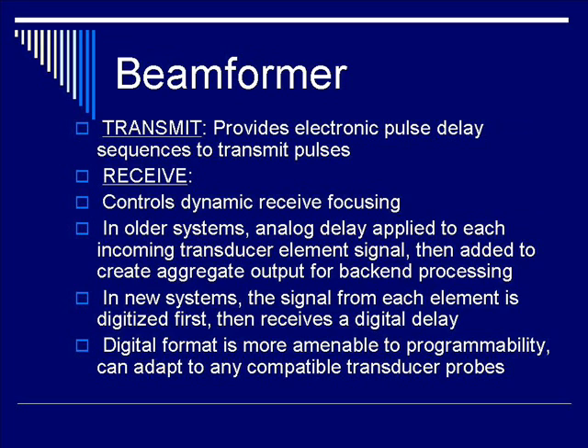It is also involved significantly in the receiving end. First of all, it controls the dynamic receive focusing. In older systems, analog delays are applied to each incoming transducer element signal and then added to create an aggregate output. In newer systems, however, the signal from each element is first digitized and then receives a digital delay. The advantage of having a digital beamformer is that it's more amenable to programmable transducer probes used in today's systems.